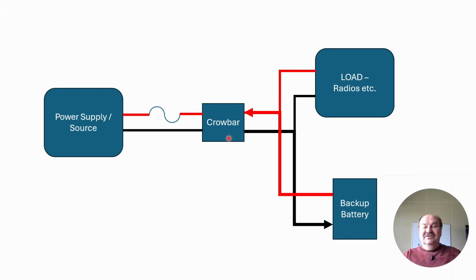So to fix this, if you're going to have a backup battery connected to your radio system directly in parallel with your power supply, you need some kind of circuit protection, either a fuse or a circuit breaker on the output of this battery. So if this crowbar ever trips, it's going to have to blow both fuses, and you need to make sure the fuses are sized right and your crowbar circuit is sized right to blow both.